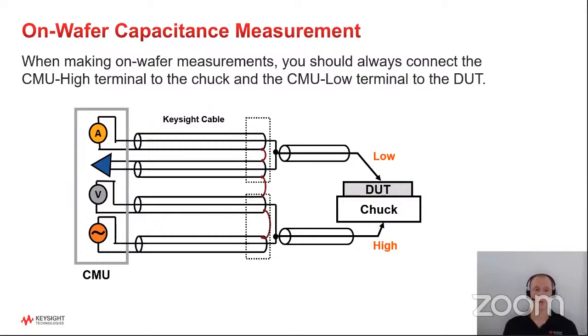The biggest thing you have to do, as shown on this diagram here, is to always make sure that you connect the low side of your capacitance meter to the actual DUT you're measuring, the wafer, and the high side to the chuck. And I'll explain why that is on the next slide.